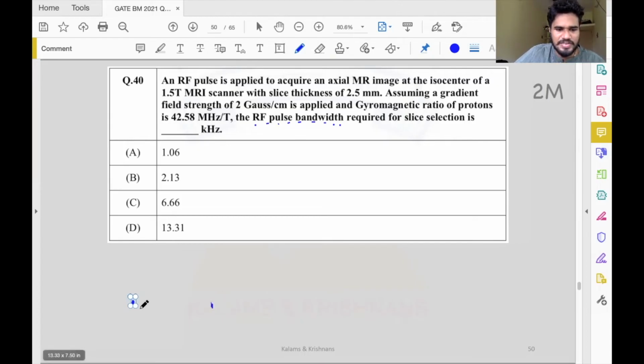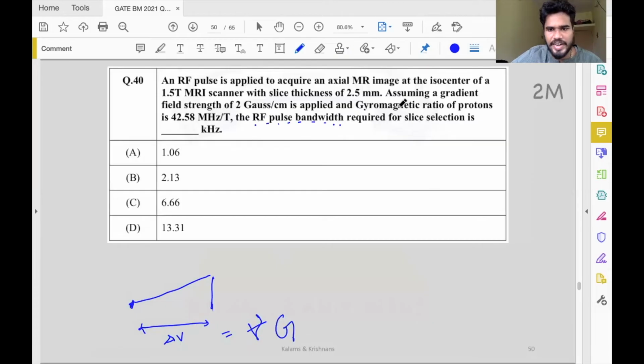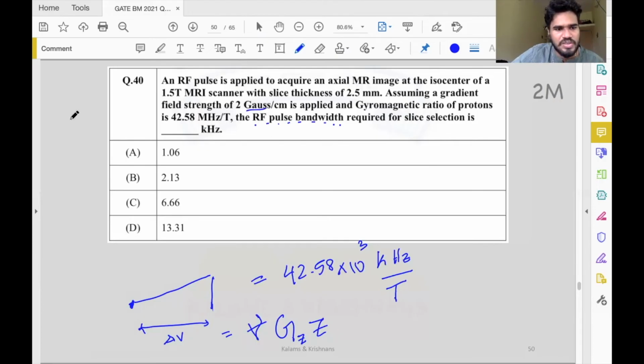Quickly, RF pulse bandwidth. Let's say this is a slice, and the frequency varies between the start of the slice and the end of the slice. The change in frequency between the start and the end is known as the bandwidth. This change in frequency is nothing but the gyromagnetic ratio of the protons times the gradient field strength, that is Gz, times the thickness of the slice, that's Z. You want the final answer in kilohertz, so 42.58 times 10 to the power 3 kilohertz per Tesla, and then Gauss. 1 Gauss is essentially 10 to the power minus 4 Tesla.